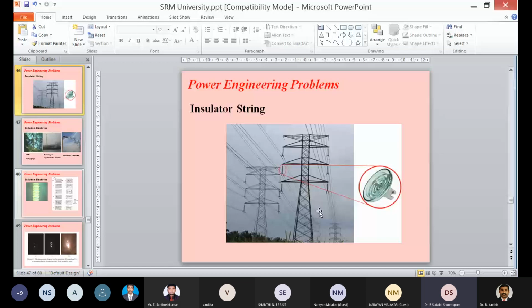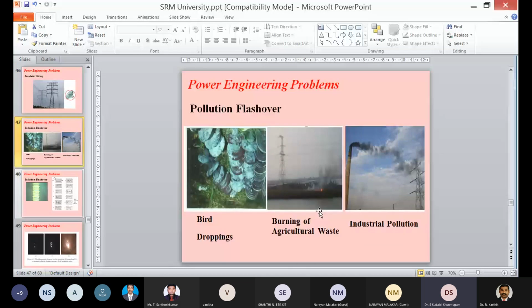So why this pollution flashover is important is, normally for a given air gap, the insulation is able to withstand the given voltage comfortably. There won't be any issue. But what is happening in field conditions is, the contaminants in the atmosphere tend to accumulate on the surface of the insulator. They form a contaminant coating or conductive coating in the early morning and late evening. Due to humidity in the atmosphere, this contaminant starts to conduct current known as leakage current, and because of this, flashover happens. This particular phenomenon is known as pollution flashover.